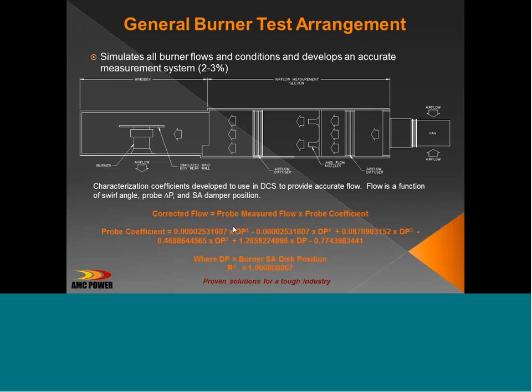damper position. We need to know what the flow is. You don't just need the DP. You need to know where the damper is, so you need the feedback signal from the damper drive. And you also need to know the swirl angle on the burner, which is typically fixed and set. But all that is put in the DCS so that we continuously monitor the airflow to each burner.